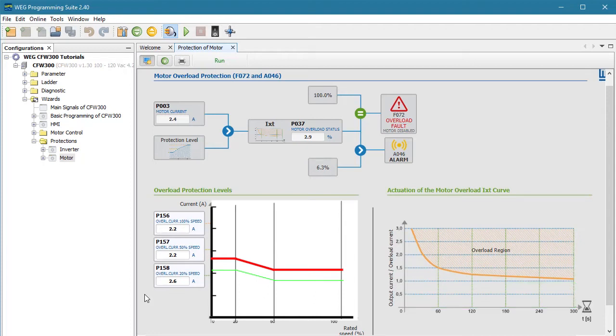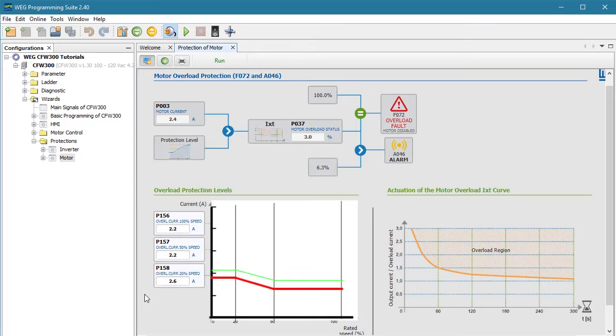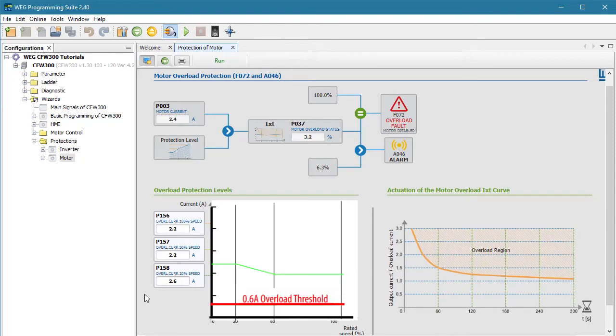Let's try this on my motor. Unfortunately I don't have a way to load this motor in my office, so I can't increase the current draw. But we can do the opposite — instead of raising the motor current, let's just lower the overload curve to force an overload condition. The added benefit is I won't actually be stressing the motor with this test; it will just look like an overload has occurred to the drive. We know this motor draws 2 amps at half speed, so let's set all the overload curve values at 0.6 amps. That means the motor current will be 3 times the overload level we set, so we would expect the fault to occur in about 10 to 15 seconds.